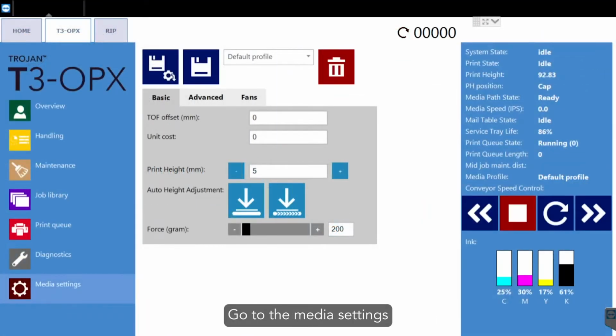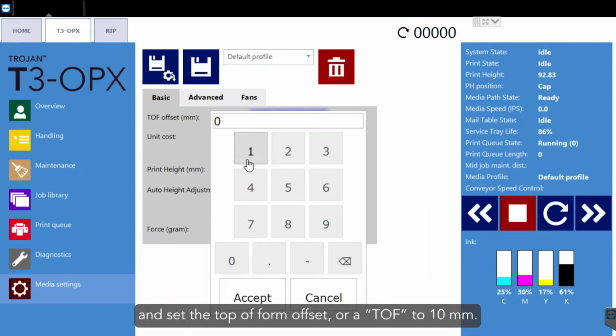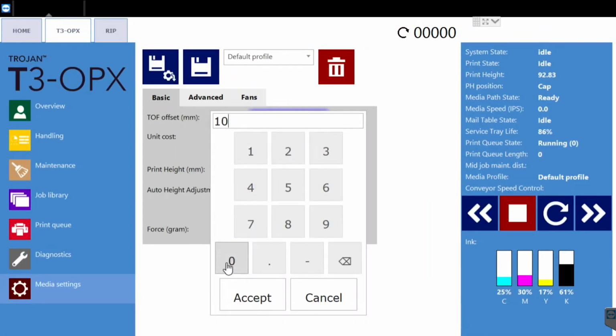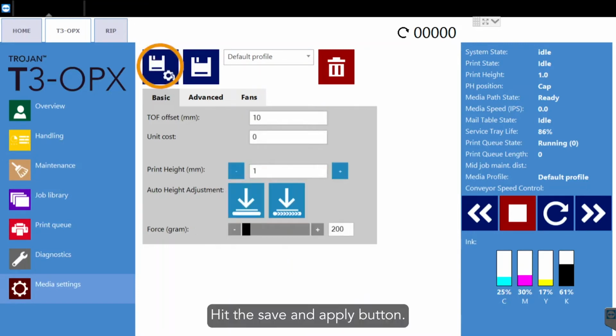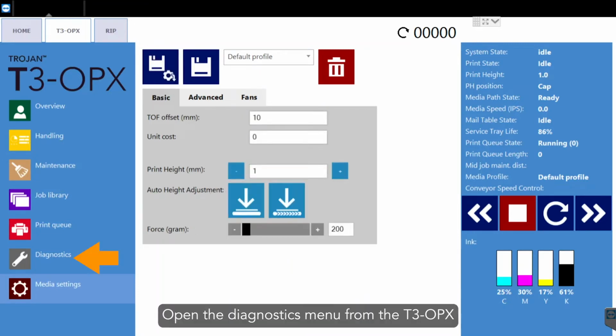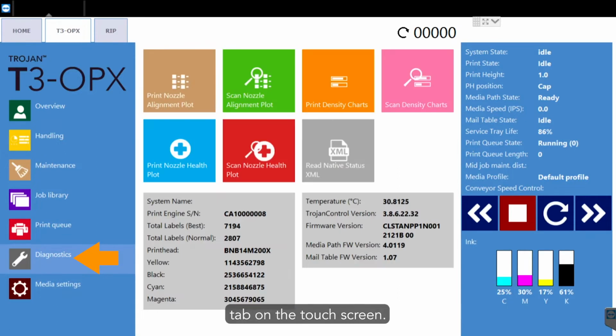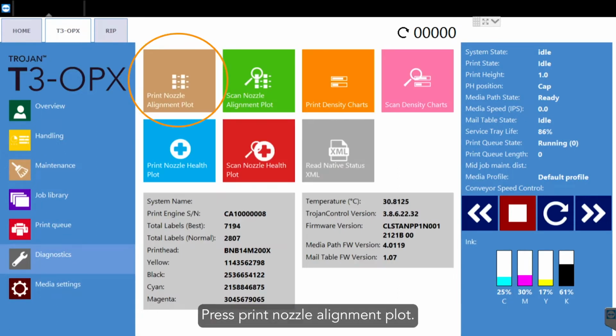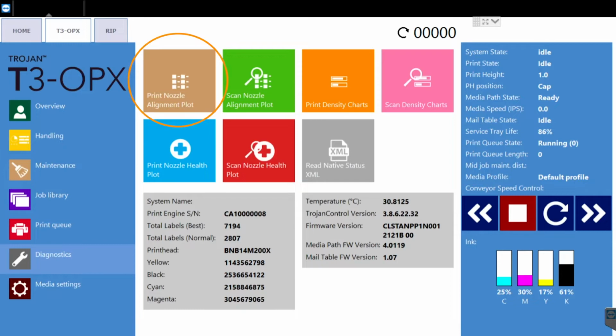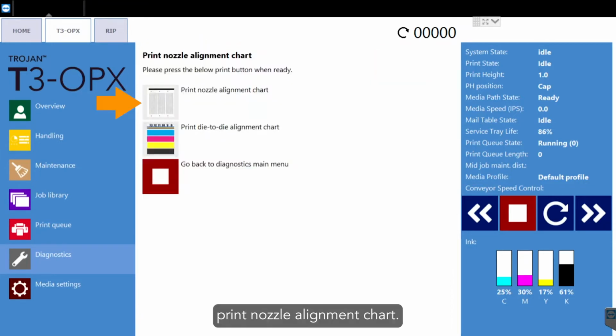Go to the media settings and set the top of form offset, or TOF offset, to 10 millimeters. Hit the Save and Apply button. Open the Diagnostics menu from the T3-OPX tab on the touchscreen. Press Print Nozzle Alignment Plot. Press Print Nozzle Alignment Chart.